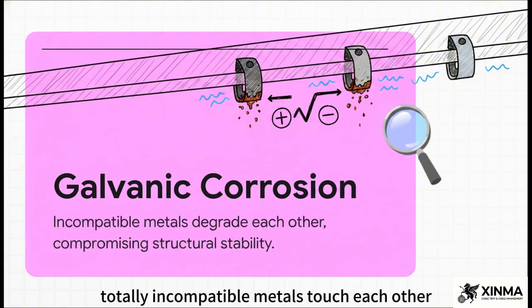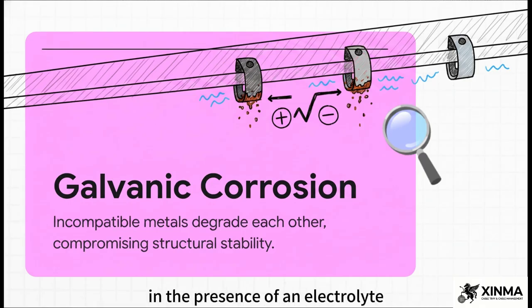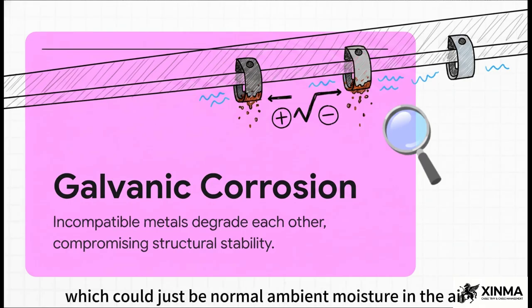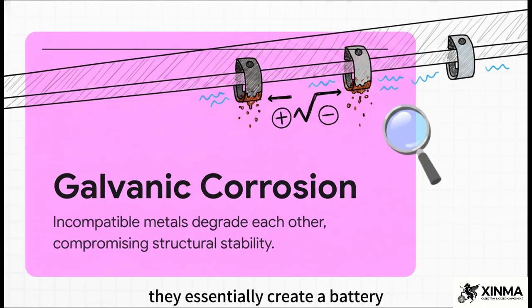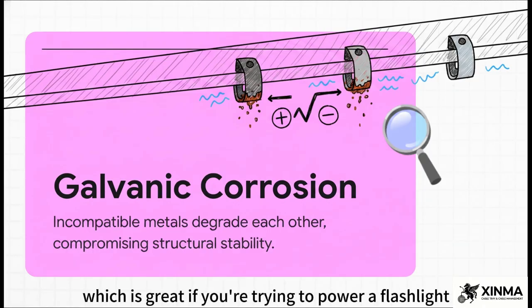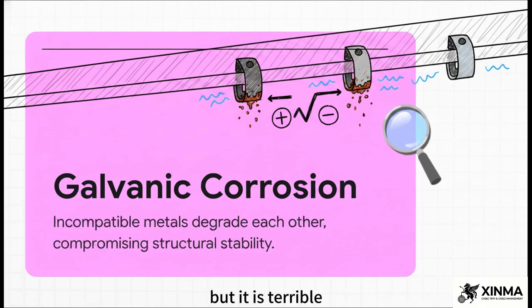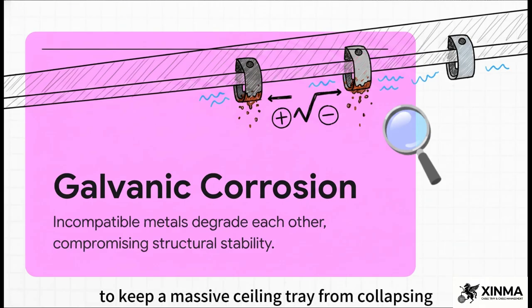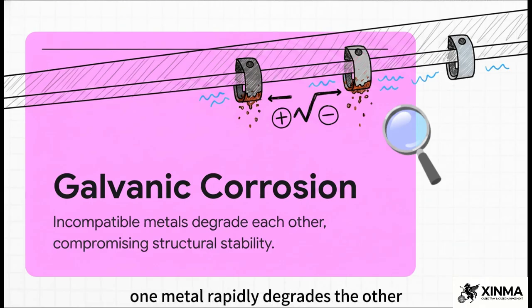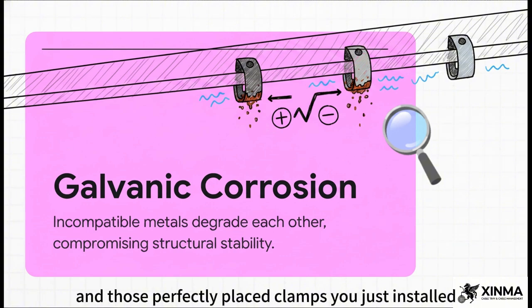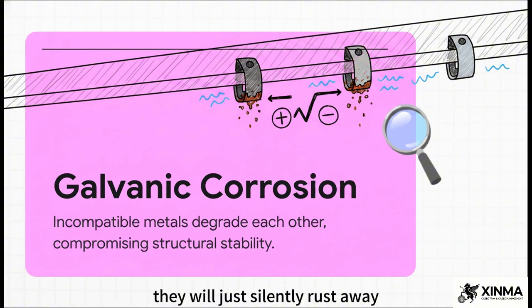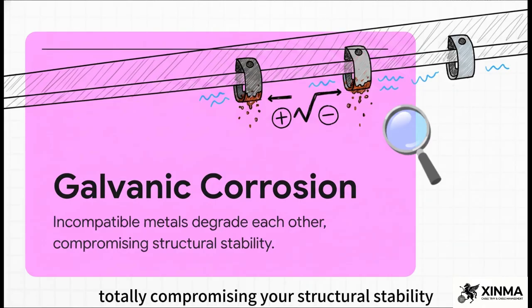This happens when two totally incompatible metals touch each other in the presence of an electrolyte, which could just be normal ambient moisture in the air. They essentially create a battery, which is great if you're trying to power a flashlight, but terrible if you're relying on those metals to keep a massive ceiling tray from collapsing. One metal rapidly degrades the other, and those perfectly placed clamps you just installed will silently rust away, totally compromising your structural stability.